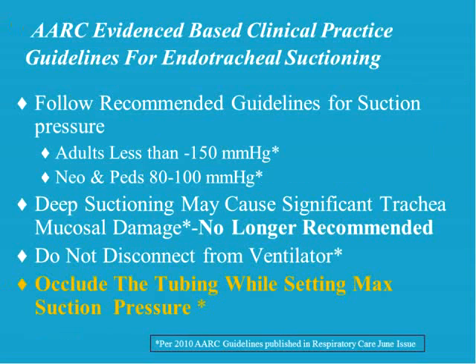Do not disconnect the patient from the ventilator. It's pretty widespread now to use inline endotracheal closed systems for suctioning. And then the last thing is to occlude the tubing while setting the maximum suction pressure. This is something that most people were either never taught or don't know, or they know it, but it's a human behavioral element and they forget to do it. You should actually occlude the tubing while setting the maximum pressure.